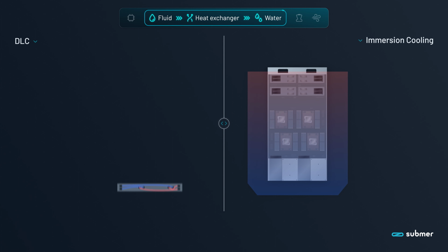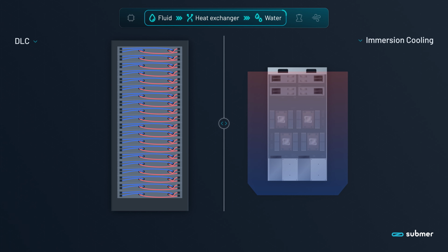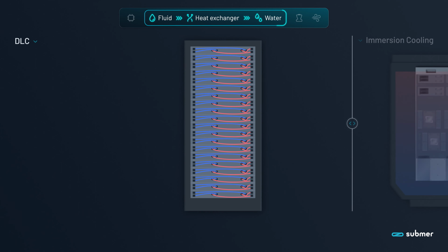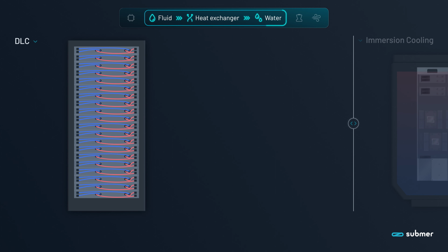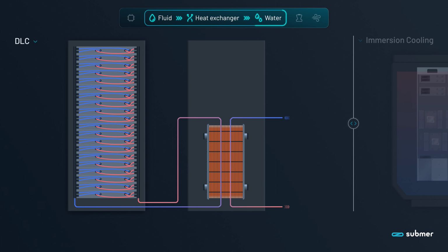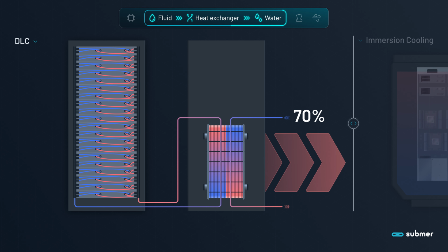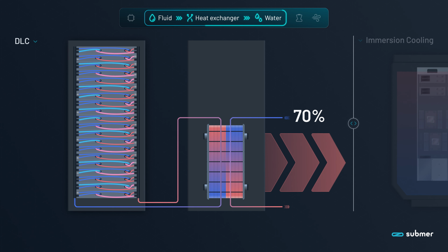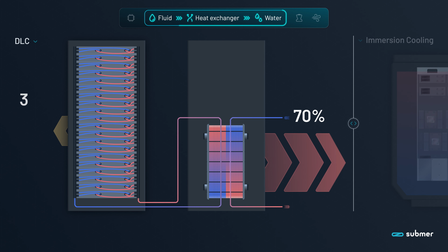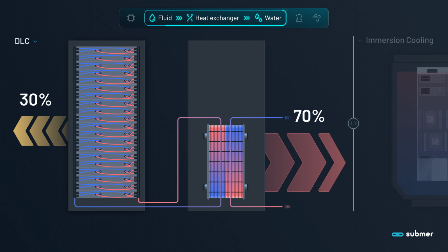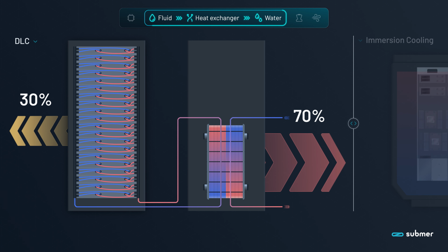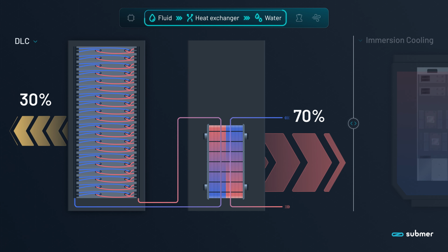A vast number of chips and servers are needed, and they are usually grouped in racks. In the case of immersion cooling, they are clustered in pods. In DLC, server pipes connect to a manifold, which links to a cooling distribution unit with a heat exchanger. Here, 70% of the heat moves from the primary fluid to the secondary fluid. However, the system's complexity increases due to the many pipes and connections, potentially affecting reliability. The remaining 30% of the heat still requires air to be removed, handled by a large traditional air cooling system.